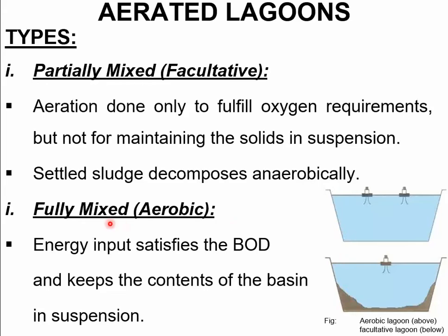Whereas in fully mixed or aerobic aerated lagoon, energy input satisfies the BOD, the oxygen requirement, and keeps the contents of the basin in suspension. Just to represent, as compared to this, there are two mechanical aerators which are sufficient to provide the oxygen required as well as to keep the contents in suspension. So there is no settlement, and all the process occurs under aerobic conditions. So these are known as aerobic aerated lagoons.